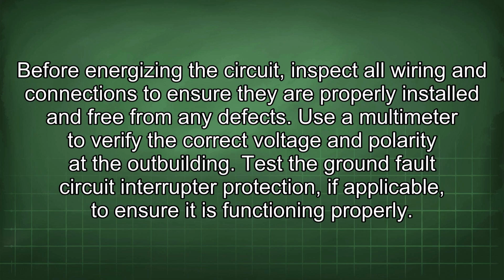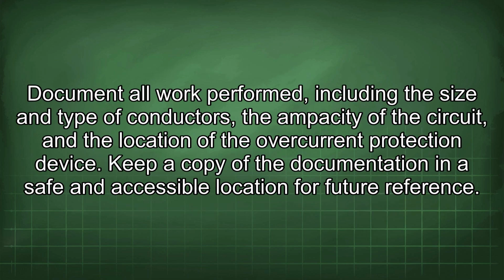Before energizing the circuit, inspect all wiring and connections to ensure they are properly installed and free from any defects. Use a multimeter to verify the correct voltage and polarity at the outbuilding. Test the ground fault circuit interrupter protection, if applicable, to ensure it is functioning properly. Document all work performed, including the size and type of conductors, the ampacity of the circuit, and the location of the overcurrent protection device. Keep a copy of the documentation in a safe and accessible location for future reference.